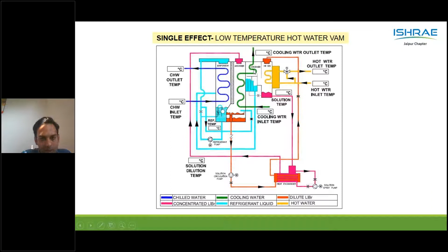So this is single effect because I have only one hot water generator, and the temperature of the heat is quite less. That is roughly around say 90 degree hot water in, 80 degree Celsius is the out. The water vapors that we produce here do not have that much further heat to further heat the lithium bromide. So hence it is a single effect vapor absorption machine.